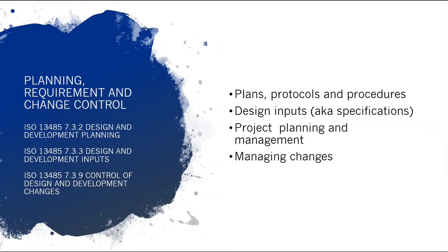As I hark on about to anyone who's prepared to listen, be really thankful when you have specifications in documents like 60601-1. It makes life a lot easier than having to make design decisions yourself. I think that really illustrates just how complex things get as you get down to the devil in the detail. It's quite a complex process, isn't it? A typical medium complexity device will have perhaps 50 to 100 user needs, and it might have 1,000 design inputs to fully define the technical requirements of that device. Okay. Each and every one of those design inputs has to be verified during verification testing.